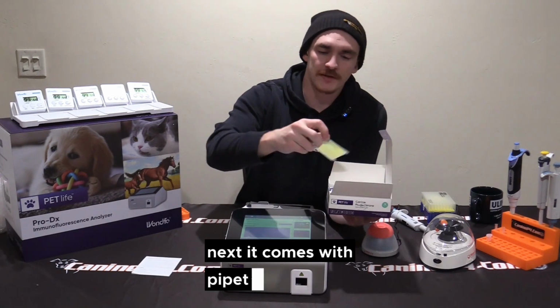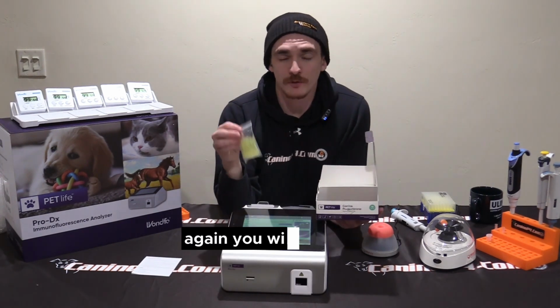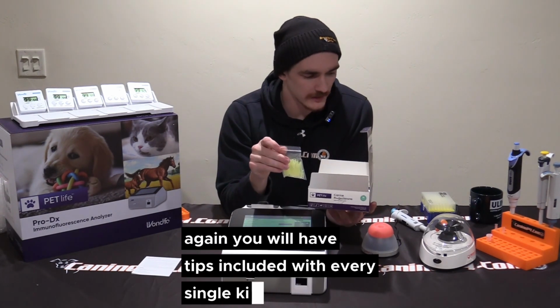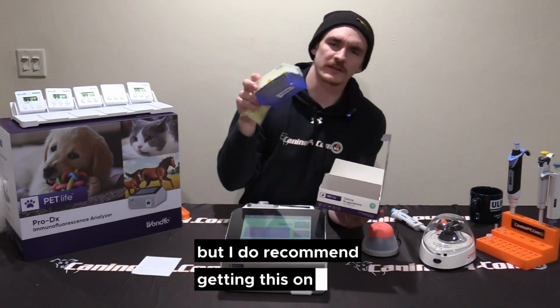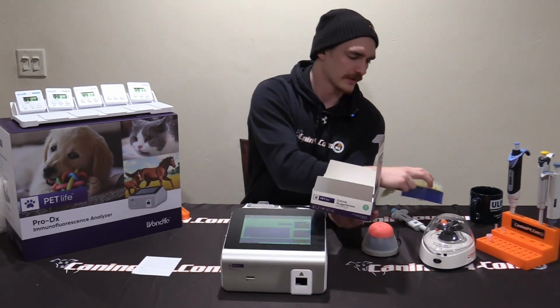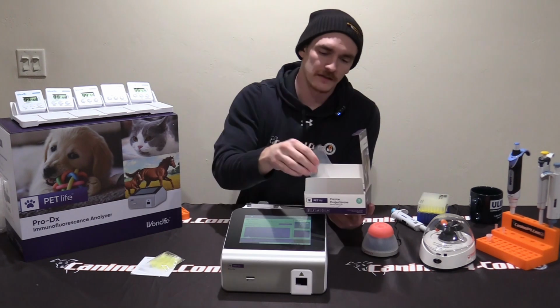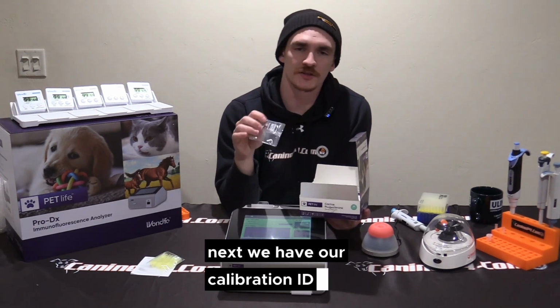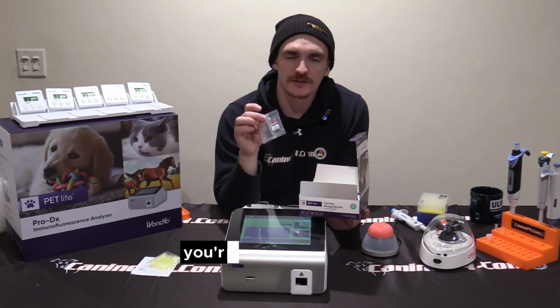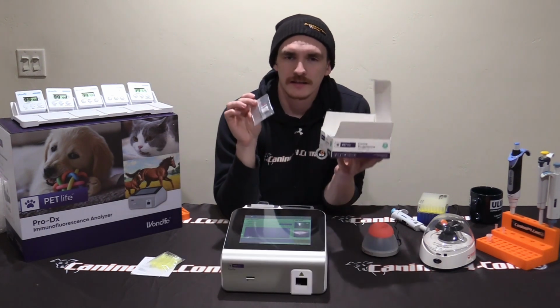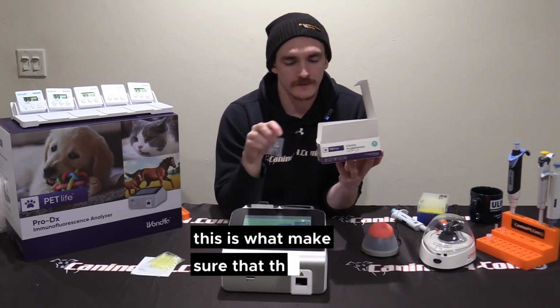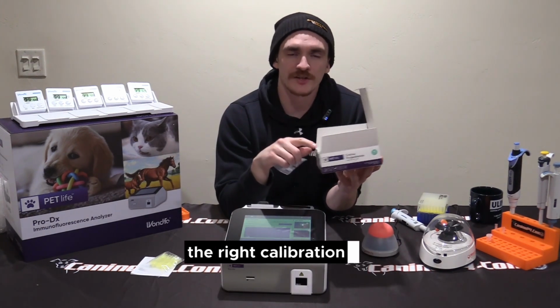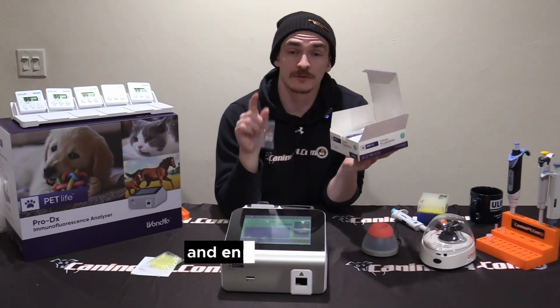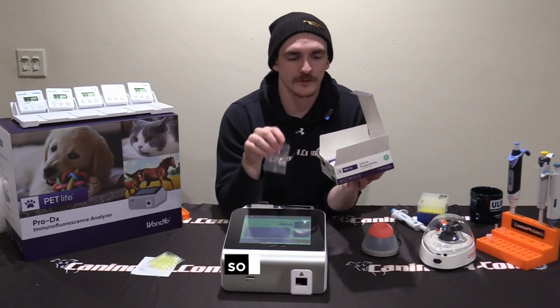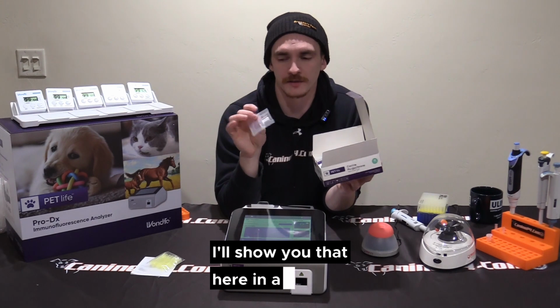Next, it comes with pipette tips. Again, you will have tips included with every single kit, but I do recommend getting this one here. It's much easier to use, and it makes the process much simpler. Next, we have our calibration ID chip. So this is the chip you're going to use to calibrate the machine. This is what makes sure that the machine is reading the right calibration for these test kits. It will ensure you have an accurate result. So make sure to calibrate. I'll show you that here in a minute.